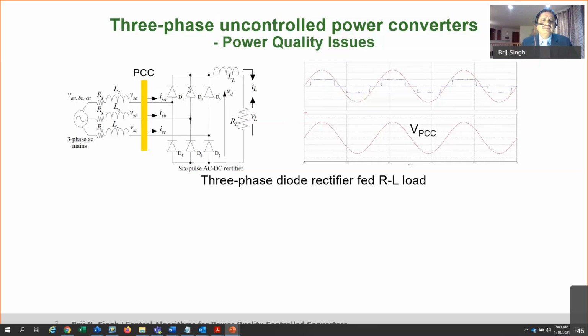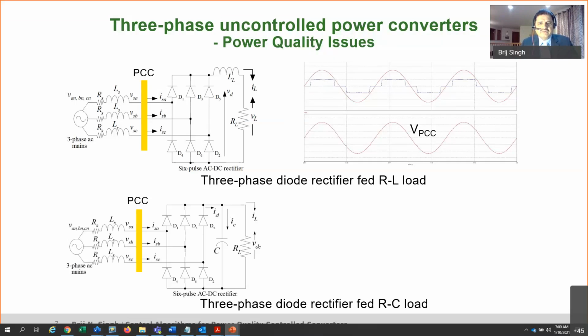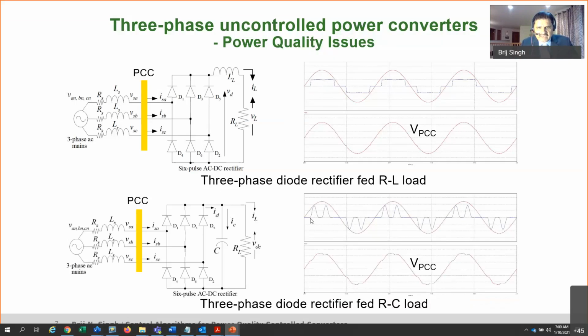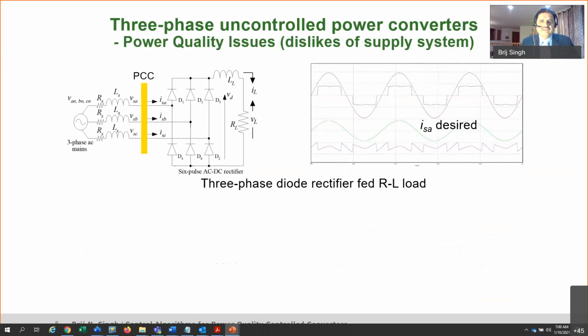And as this current gets higher and higher, more distortion happens. And imagine that if it's a thyristor type load, then that generates far more, because commutation of a thyristor is really very fast. It's a very hard switching device. And then in the RC load, it is even more obvious, because the RC load has this type of current. So you see how voltage got distorted right here versus this. Like this is a load, this is the source voltage here, this top waveform, and this is the current that is here, and this is the source voltage at PCC, which is not a desirable situation. So what do you do about it, right? What is missing here is that the load doesn't demand this difference of the current.